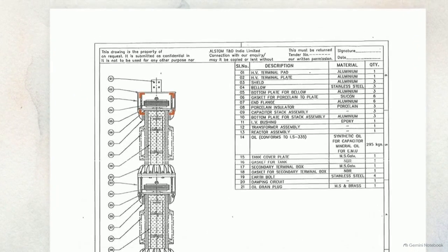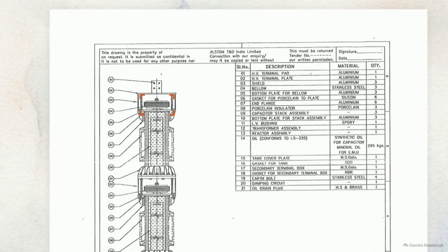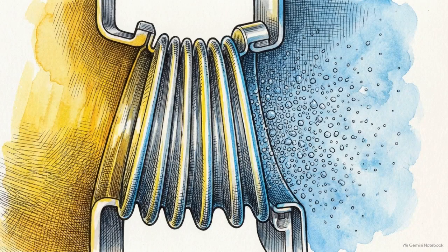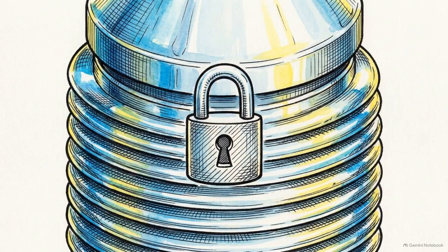As heated oil increases in volume, it pushes against the bellows. The metal accordion compresses inward, giving the oil room to expand and keeping internal pressure constant. This flexible mechanical seal prevents the oil from ever coming into contact with atmospheric moisture, which would ruin its dielectric strength. By acting as mechanical lungs, the bellows allow the entire internal system to remain hermetically sealed and maintenance-free for decades.